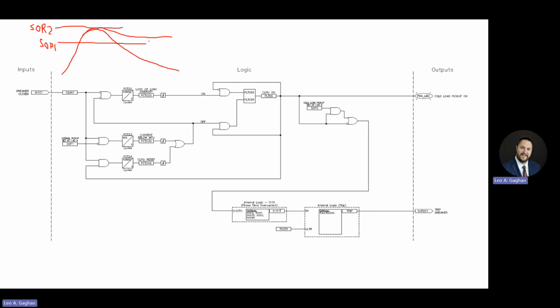It's not cold load that's causing this higher magnitude. It's actually a fault value. But we can't allow that situation to hang out forever. So in that situation, cold load pickup will actually have a maximum amount of time that it can be on before it resets itself. So if it's on with the breaker closed, that situation can only happen for a period of time before it automatically resets itself, regardless of if it's above or below our 50P. So that's kind of the basis of the cold load pickup logic. We would have an LED to let us know the cold load pickup is active.